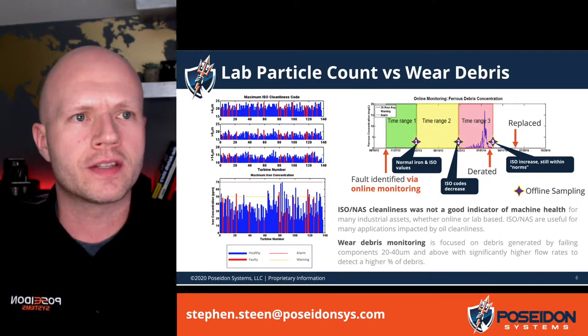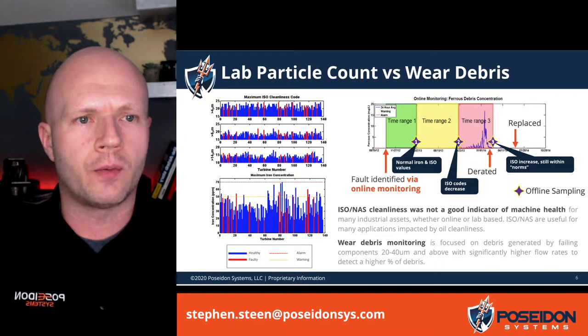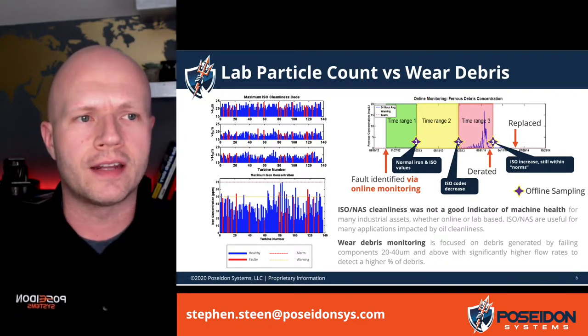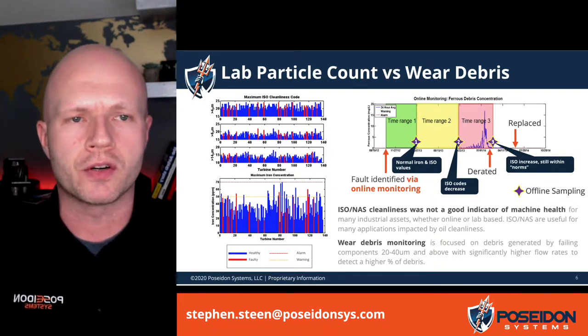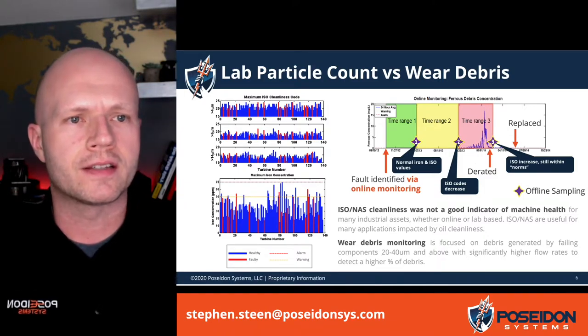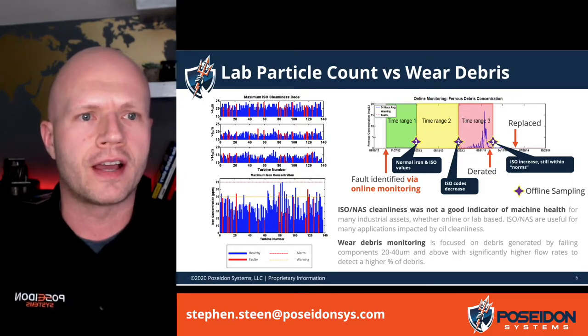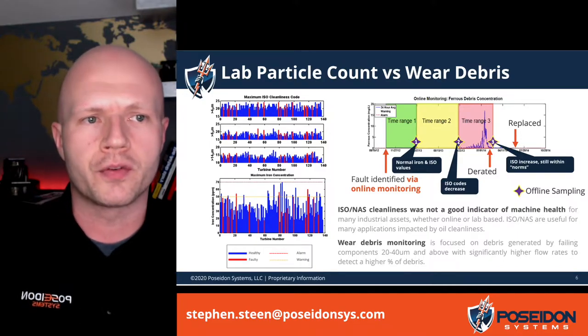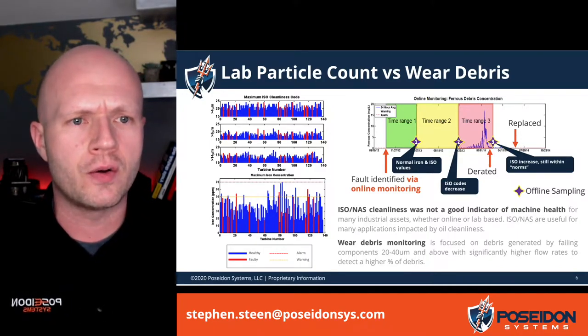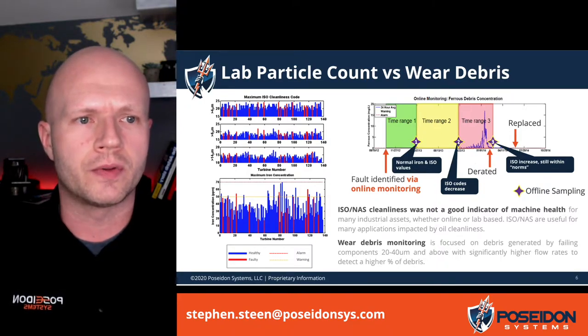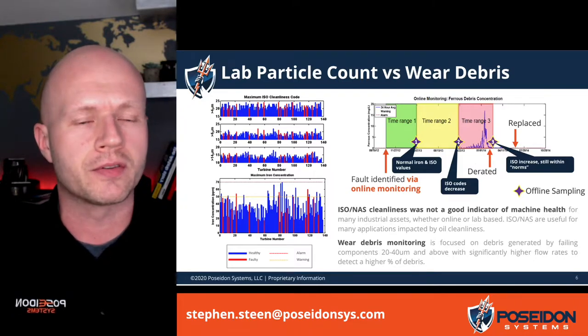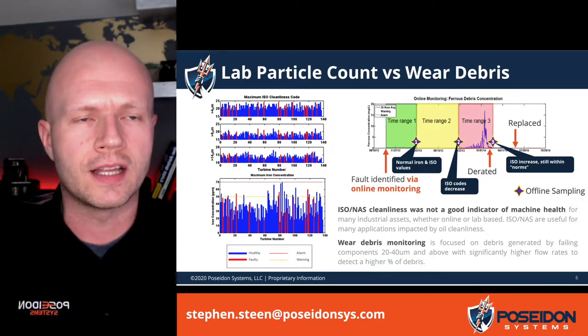Here's a nice survey of quite a few industrial assets — roughly 140 of them. We took a look at what lab analysis gives you in return versus what an online wear debris sensor would give you. We're really comparing the output from lab analysis and how good it is at detecting a fault or failure — using a crusher gearbox as an example. On the left hand side you can see the max values for all the different ISO cleanliness levels as well as the maximum iron concentration, pulled from a three-year period. We compared that to the known fault or failure history for the fleet of industrial gearboxes and found very little correlation to those measurements with the actual health. As you can see, the failed gearboxes are in red — some of those are very low, some are very high, and none of them really cross the fault level you get from a lab.